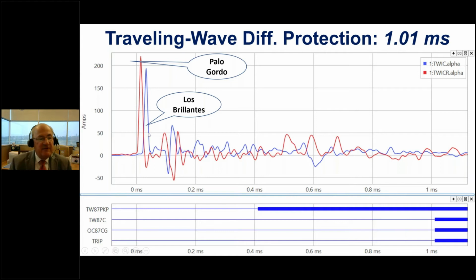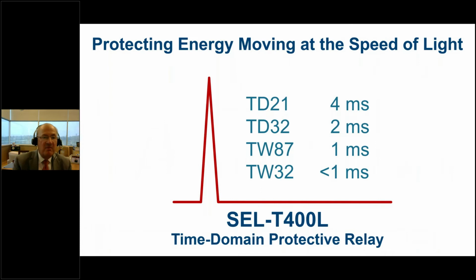So anyhow, we use this information. These are the same polarity, meaning they're both going up, not one up, one down. And some other things in order to make a trip decision. We really have a good answer after about 400 microseconds, and we're able to securely, dependably trip in just over a millisecond. And that's the traveling wave differential element.